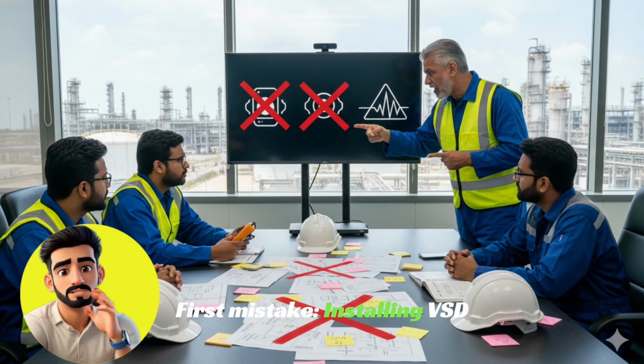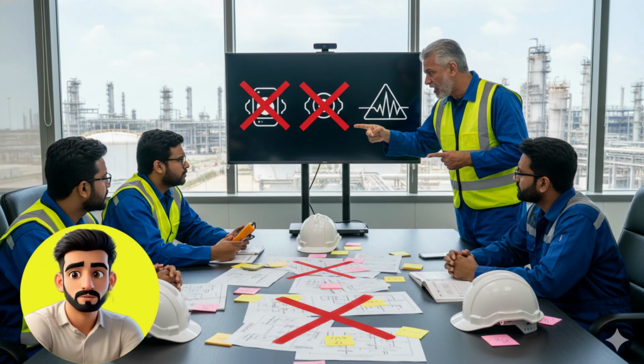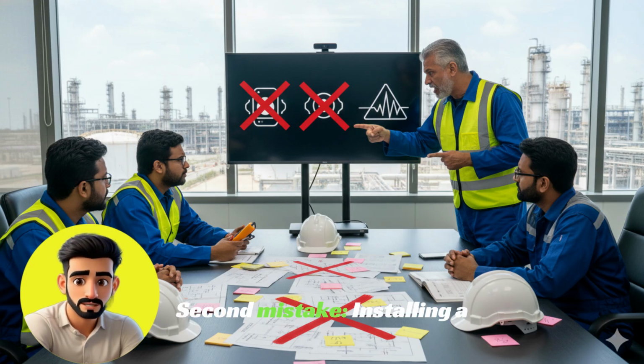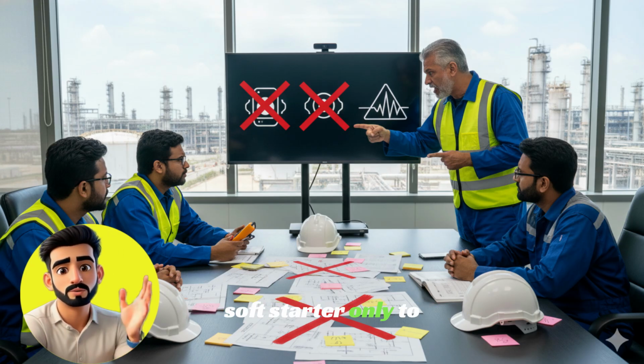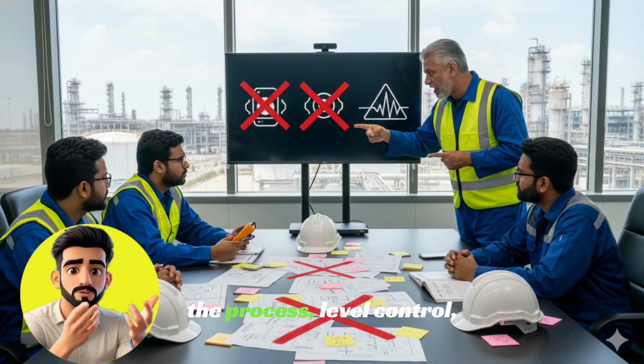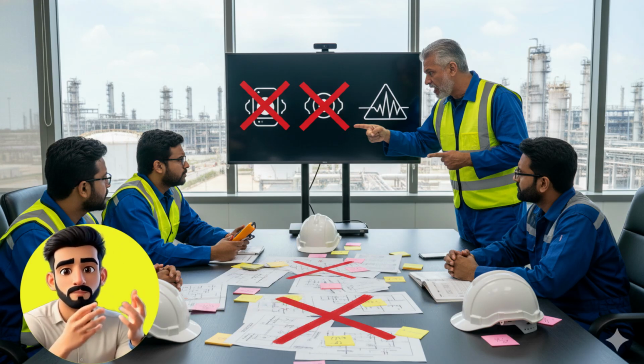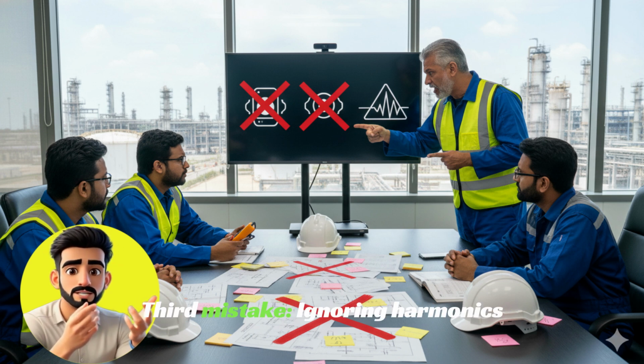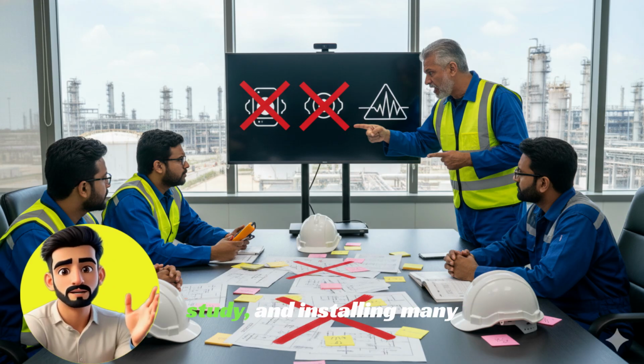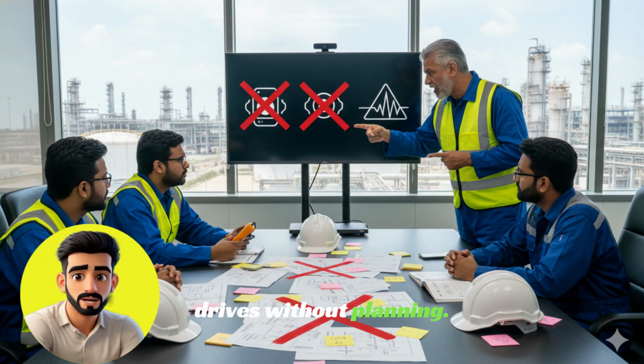First mistake, installing VSD just to look modern, whereas a soft starter is completely sufficient. Second mistake, installing a soft starter only to save costs, when in the process, level control, pressure control, or flow control are critical. Third mistake, ignoring harmonic study and installing many drives without planning.